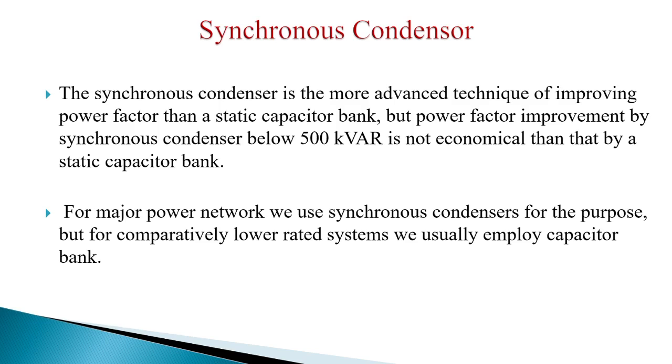So, the synchronous condenser is a more advanced technique of improving power factor than a static capacitor bank. But power factor improvement by a synchronous condenser below 500 kVAR is not more economical than that by a static capacitor bank.